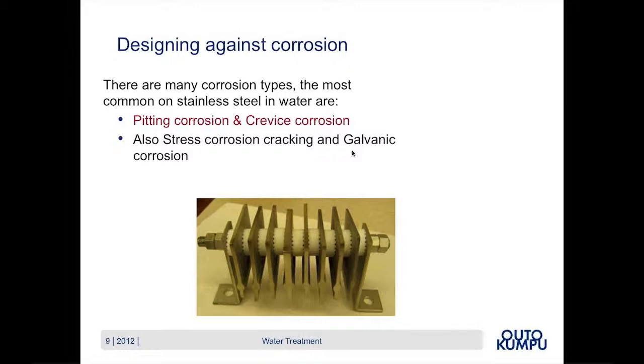This rack is then shipped to the plant site where the new installation is to be. Leaving the rack exposed to the local conditions for a specified period, subjecting the material to a precise replication of the service condition, allows us to assess which grade would perform best. This performance would be measured in both technical and, of course, commercial terms, identifying the optimal and cost-effective solutions. Of course, it's usually possible to look at current service experience as well and to understand which materials have been used already in similar installations in the past and how they've performed.